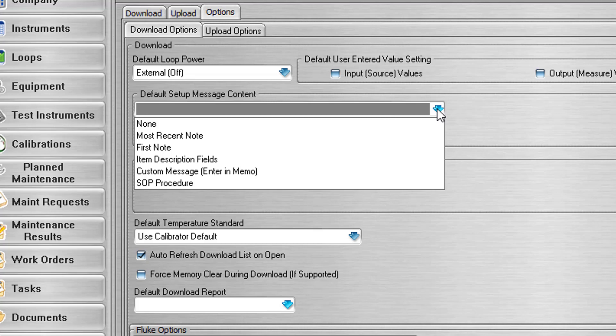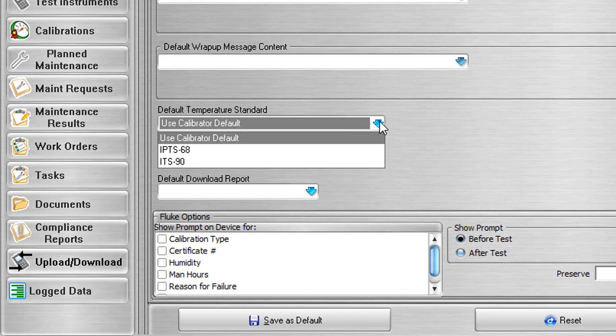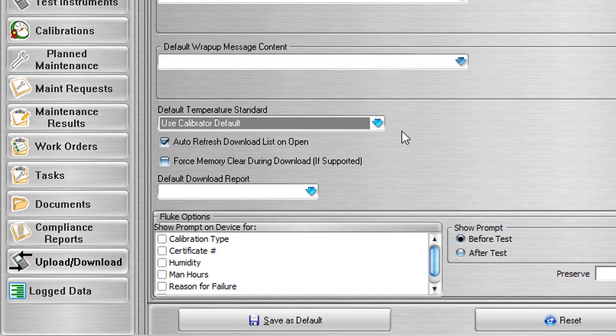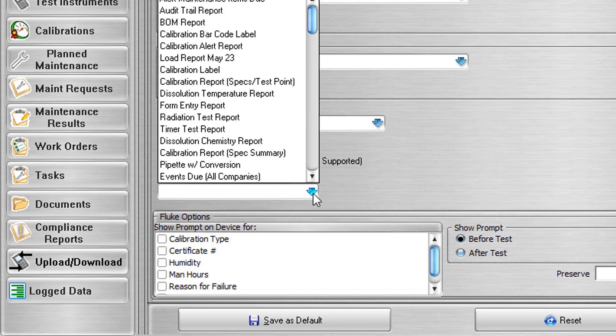The Default Temperature Standard field may be set to use the current calibrator's default but may also be overridden for the current download session to ITS90 or IPTS68. When the Forced Memory Clear During Download checkbox is checked, the user will receive a message to force the clearing of the memory on the calibrator. When data is stored on the calibrator and more tags are downloaded, you have the ability to save the previously calibrated data in a cache file on your computer; when uploading results, the program will ask if you'd like to include data from the cache file. The memory can also be cleared at any time via the Features menu. The Default Download Report field is populated with a compatible report, such as the session download report, which is generated upon completion of a download.